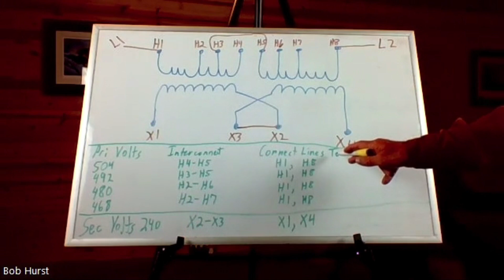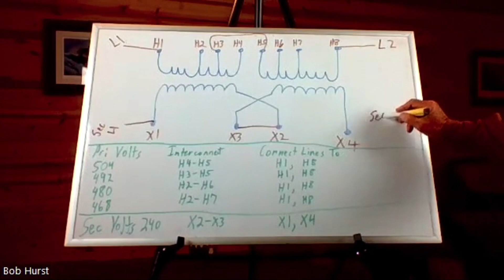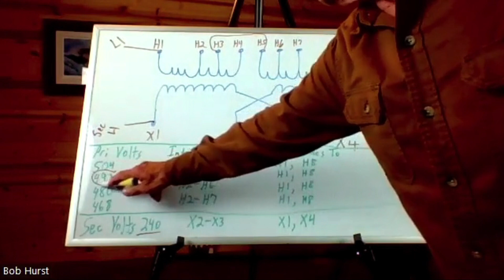And then down here it says secondary volts, connect lines to X1. That will be our secondary L1 connected to that, and this will be our secondary L2 connected to that, which will give us 240 volts on the secondary, since this is what we had as power coming in.